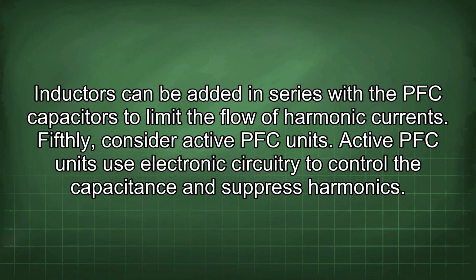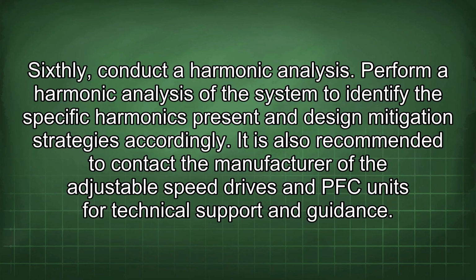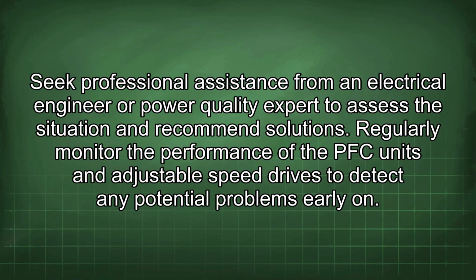Fifthly, consider active PFC units. Active PFC units use electronic circuitry to control the capacitance and suppress harmonics. Sixthly, conduct a harmonic analysis. Perform a harmonic analysis of the system to identify the specific harmonics present and design mitigation strategies accordingly. It is also recommended to contact the manufacturer of the adjustable speed drives and PFC units for technical support and guidance. Seek professional assistance from an electrical engineer or power quality expert to assess the situation and recommend solutions.